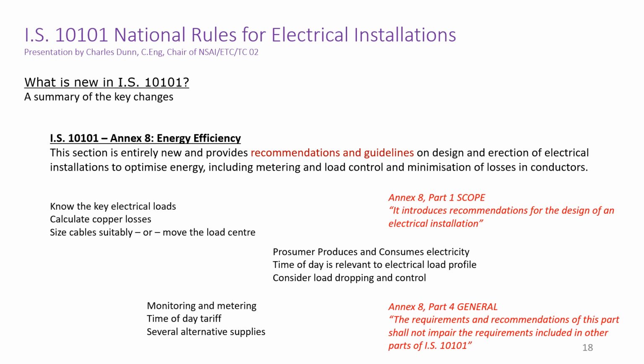For designers, though, Annex 8 is all good stuff, and it asks you to do all those things you were actually supposed to be doing anyway. Reducing copper losses by cable sizing correctly, centralising the mains power supply on the key electrical loads, designing in electrical monitoring and metering. A notable consideration is to consider the need for load shedding or control where alternative energy may be introduced in the installation later. CHP, PV or wind energy may be connected later, for example. Larger electrical loads, EV charging, water heating, etc. may need to be disconnected when alternative energy is not available.